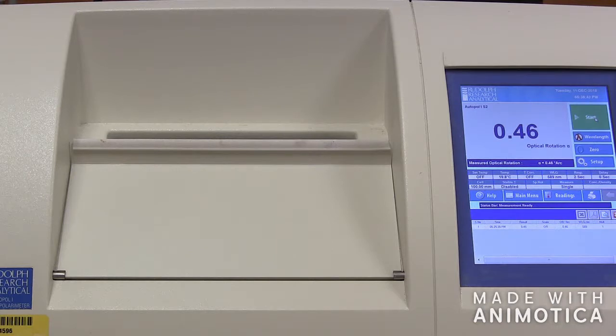Before collecting your sample's data, you must zero the instrument. To zero the polarimeter, fill the observation tube with solvent, watch for any air bubbles trapped in the tube, then cap the tube with the stopper, place the tube in the polarimeter, and close the door.